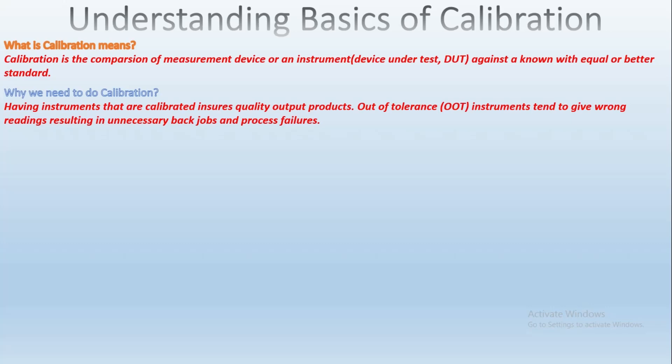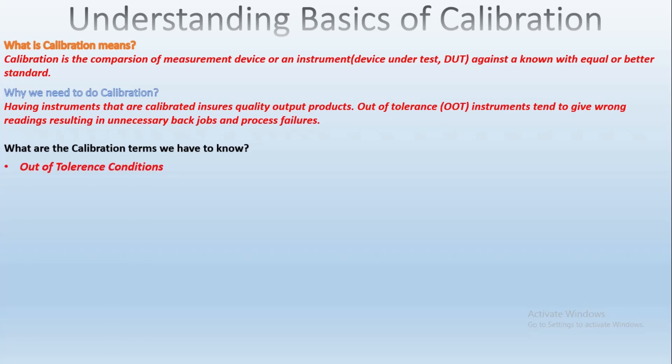There are some important common calibration terms we need to know before working on calibration. The first one is out of tolerance condition. If the results are outside of the instrument's performance specifications, it is considered an OOT — out of tolerance — condition, and will result in the need to adjust the instrument back into specification.